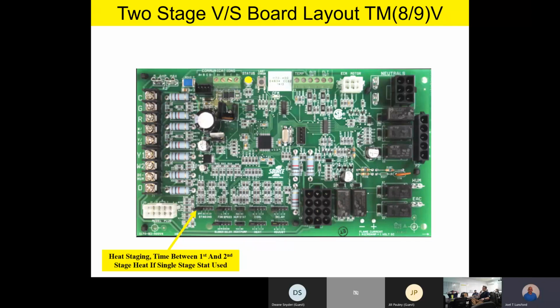Let me say that again. If this jumper is in the off position and you're stuck with a single stage thermostat, you will never get out of single stage heat. However, if you have it on the 10, 15, or 20-minute position, say it's on the 10-minute position, and you get a call for heating on W1. If the call for heating is still there after 10 minutes, it'll automatically go to second stage to finish off the heating call. Then once the thermostat's satisfied, it goes through its normal shutdown procedure and so on. So the staging jumper gives you some options if you're stuck with a single stage thermostat.